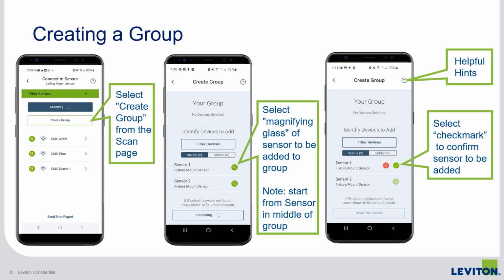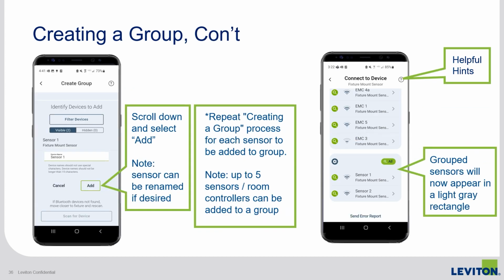To create a group, start from the initial scan page. This is where you should identify and start with the sensor or room controller that will be in the middle of the group. Once you have confirmed the correct device, click the check mark to start forming the group. At this point, you also have the option to rename the sensor. If you have no changes, click the Add button and the group is now created. This is the initial device where the group was started from.